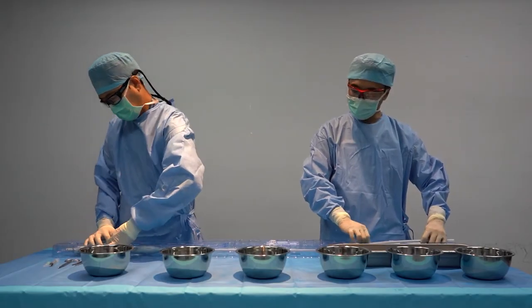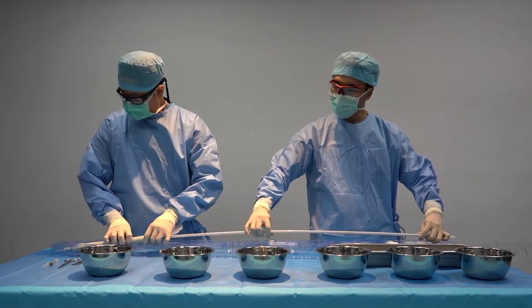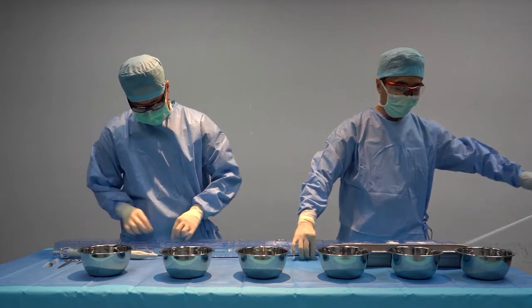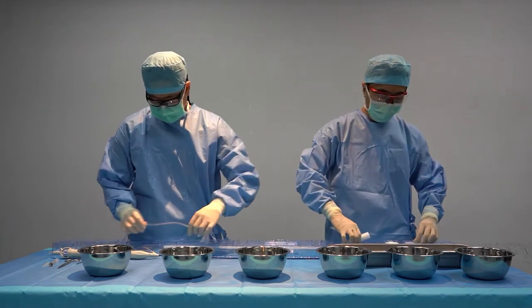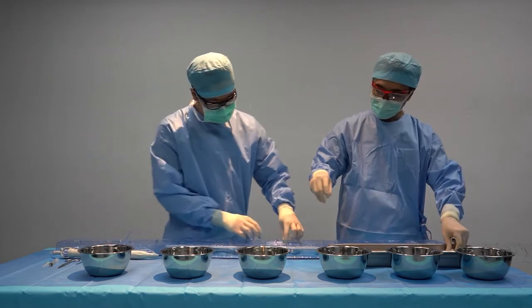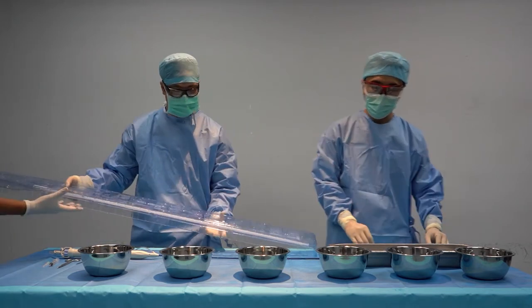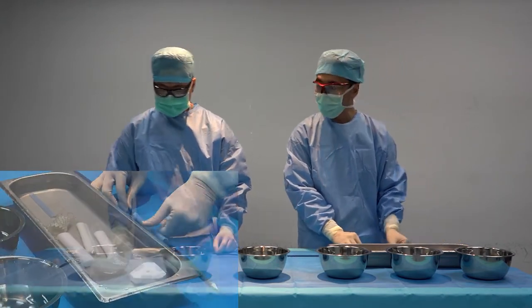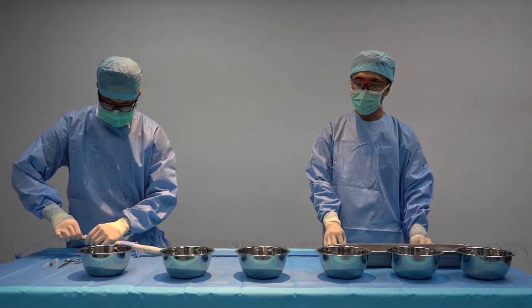The delivery catheter system is gently taken out from the plastic tray. The other apparatus, including the mandrels, crimper, and tubes, are placed into the loading basin with the exception of the purge tube. Insert the loading tube from the distal end of the delivery catheter system. Connect the purge tube to the delivery system near the rotating knob.